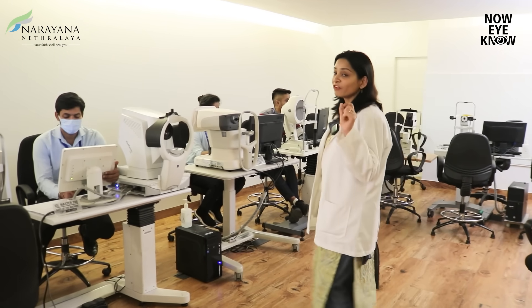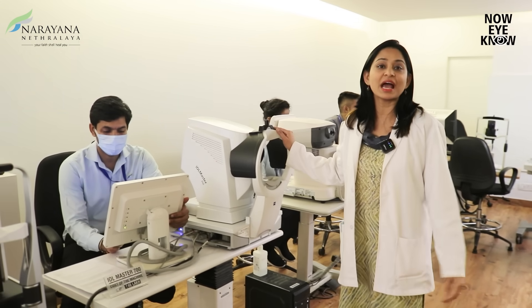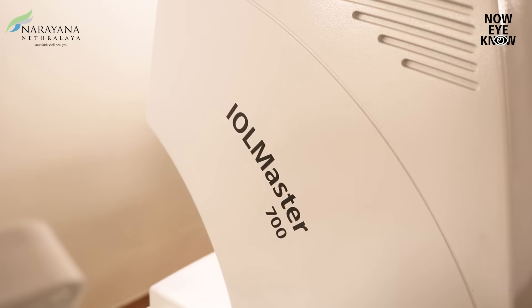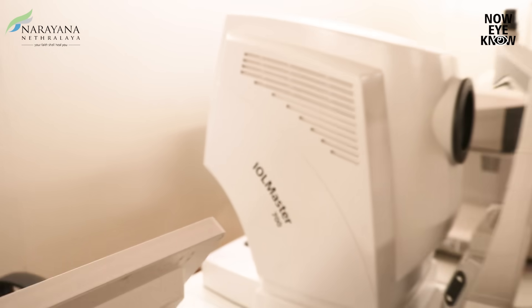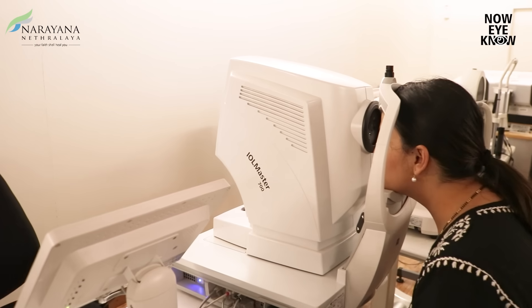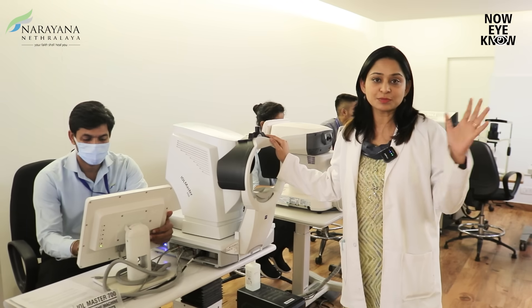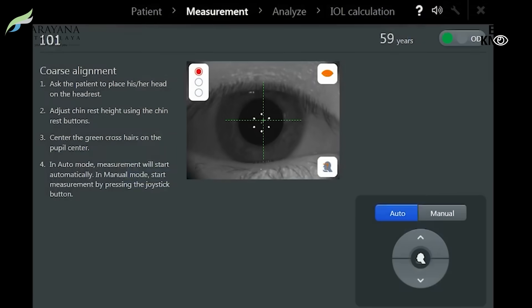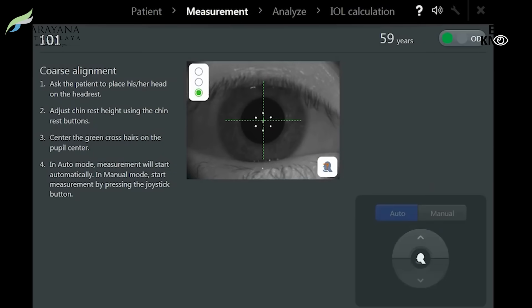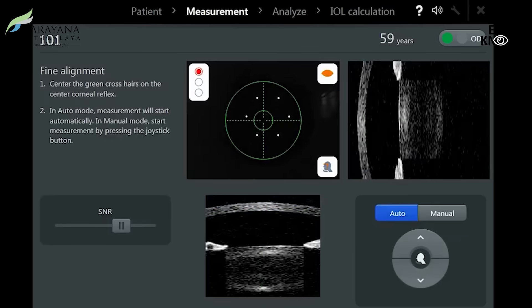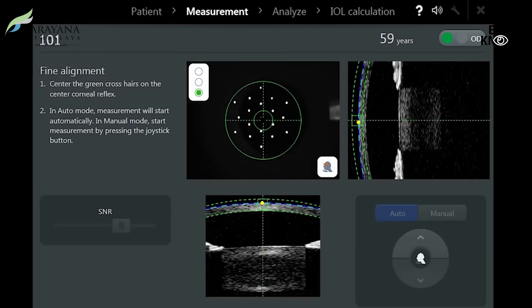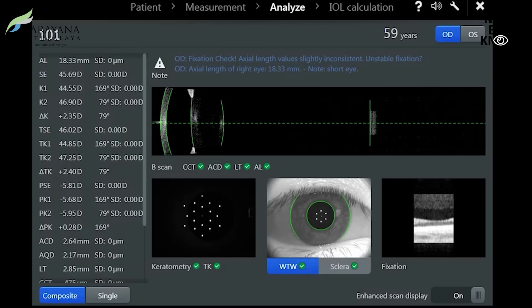Choosing the right IOL power plays a very crucial role in planning cataract surgery. To do that, we have our Biometer IOL Master 700, which is a Swept-Source OCT. This machine is very important because it takes around 2,000 scans in around 40 to 50 seconds, measuring various parameters in the eye that are important for choosing the IOL power to be implanted.